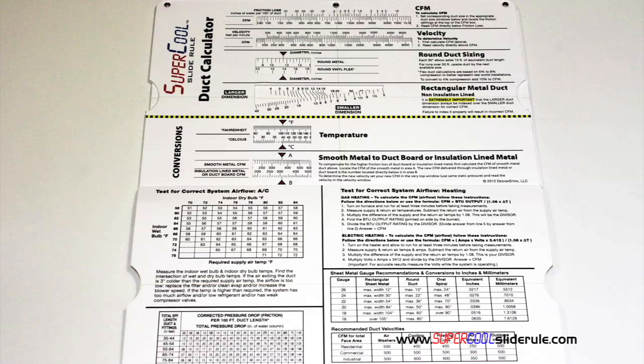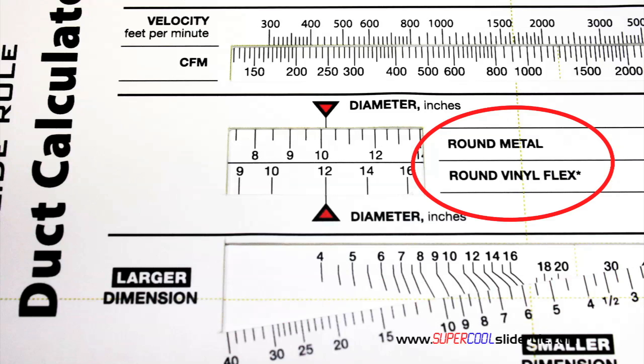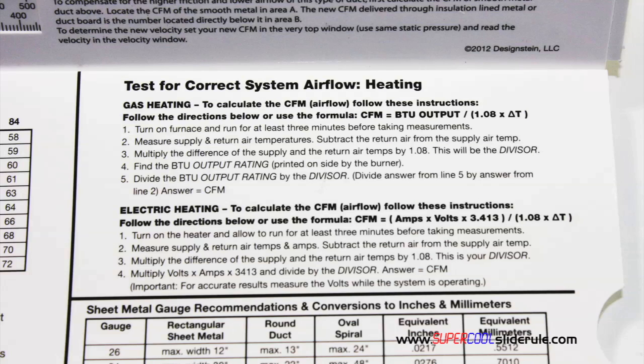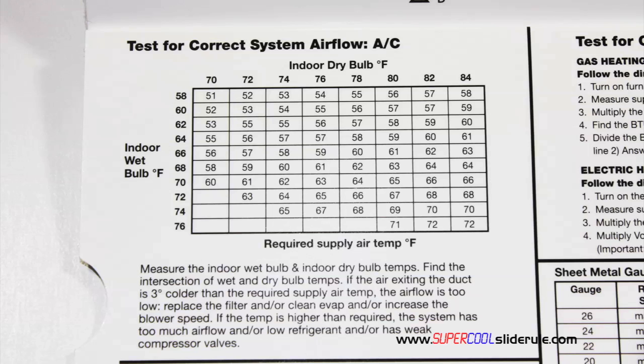Inside, it is packed with even more information. It performs sizing of both metal and flexible duct. It has the only direct reading conversion from smooth metal to insulation-lined metal we've ever seen. The majority of technicians have never been taught that if the insulation is on the inside of the ductwork, you cannot size it with a regular duct calculator. It also has step-by-step directions for determining airflow through a gas furnace, electric furnace, or an air conditioning unit.